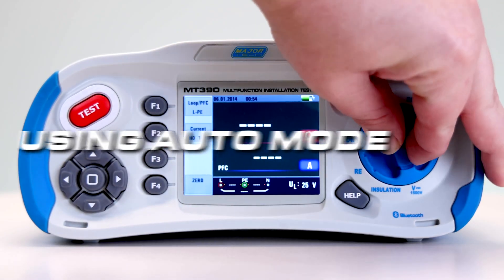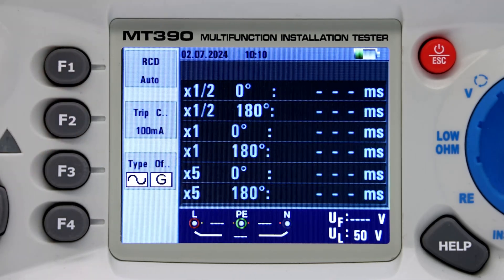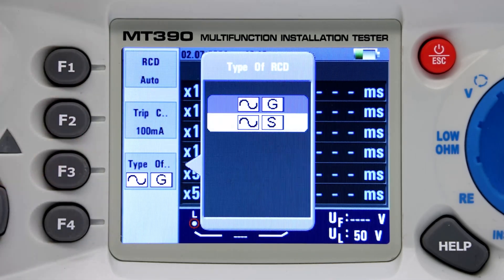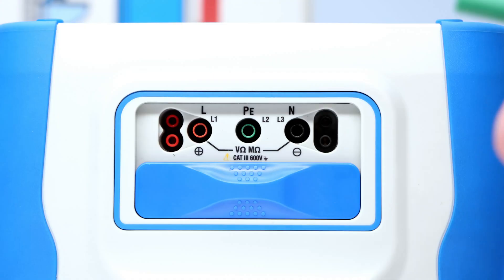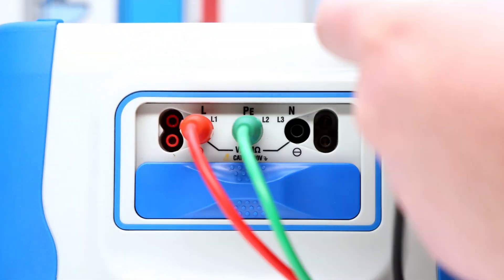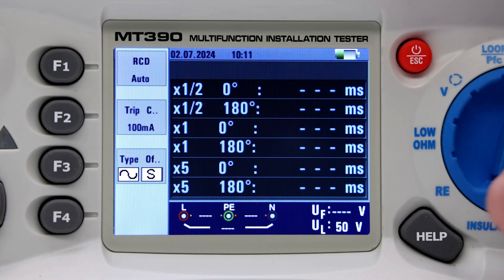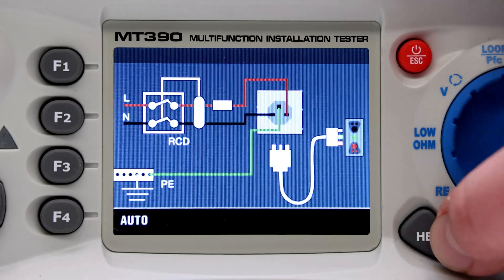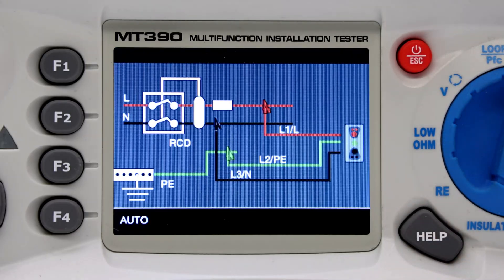Using the Auto mode, turn the rotary switch to the RCD position. Using the F2 and F3 buttons, select the rating and the type of RCD. Connect the test leads. Press the help button to display the correct wiring diagram. When the voltage of live and protective earth appear on the lower left, the unit is ready to test.